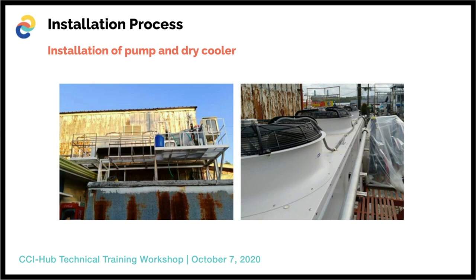Correspondingly, due to the result of our four previous water loop projects, we decided to focus on control over the dry cooler operations. The main reason is that Subic Bay is a nearby ocean range with high humidity. And also, this will achieve the manufacturer's required water entering temperature, which is about 25 to 28 degrees Celsius on the liquid-cooled condensers.